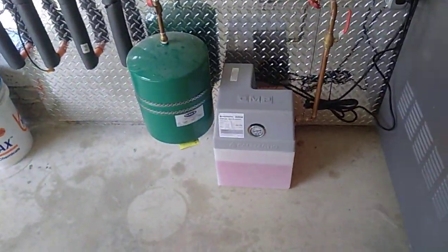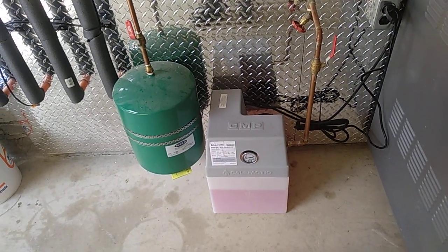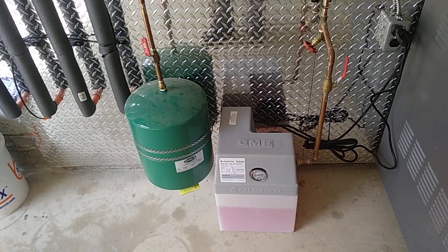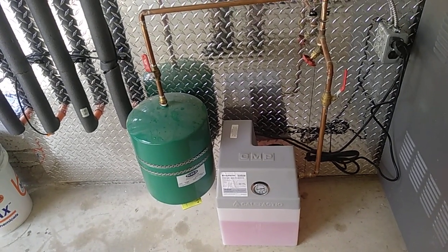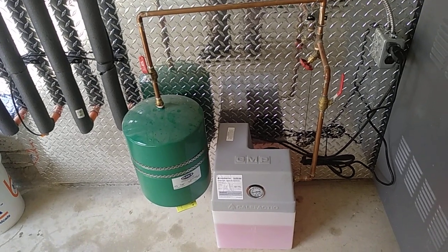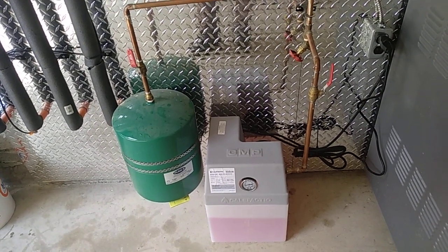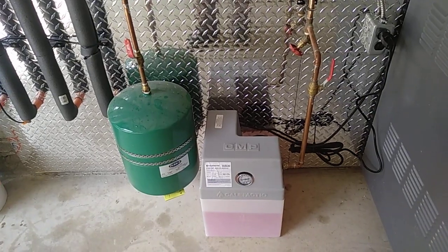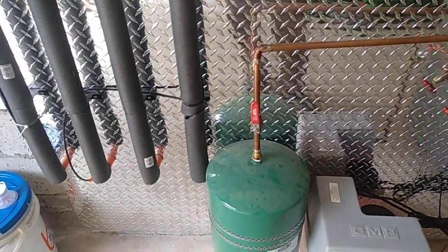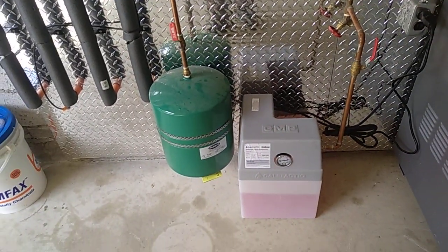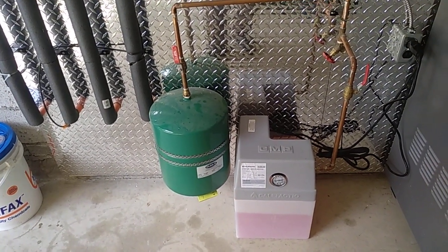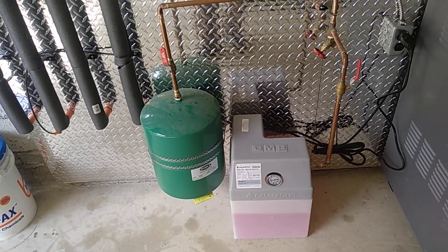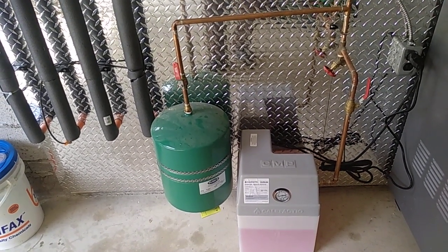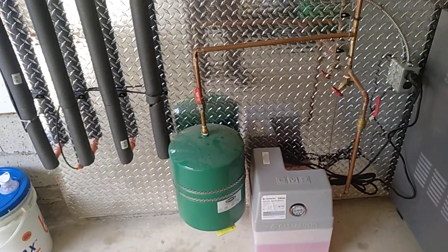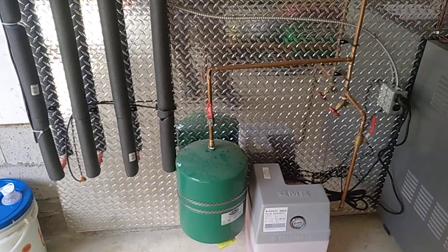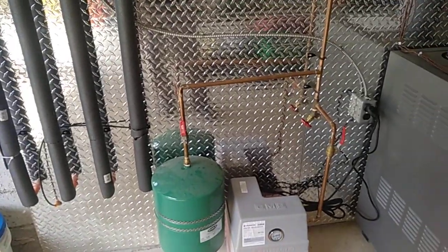There is a glycol makeup little feeder down here that ensures that the system is always topped up with glycol. There are no air bubbles in the system that would damage the pump and degrade the efficiency of the boiler. We're keeping the pressure at 15 psi. There is also an expansion tank that will absorb the expanding glycol when hot and reintroduce that absorbed glycol into the system when the system is turned off and the glycol contracts because it's cold.